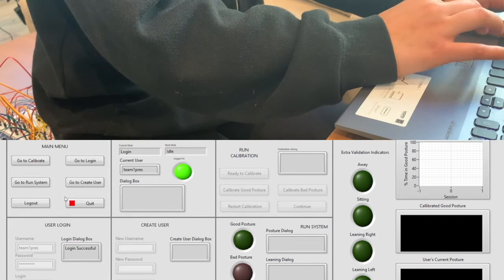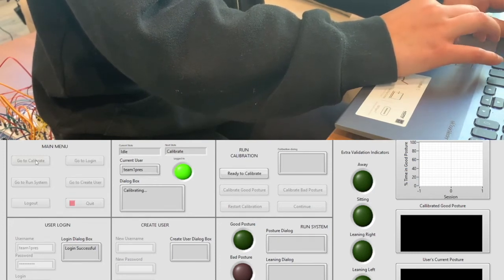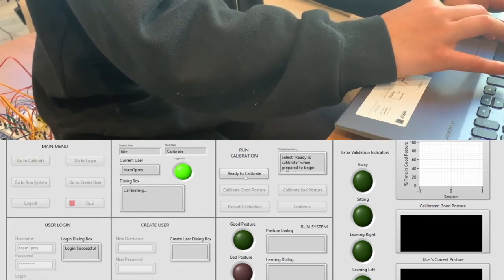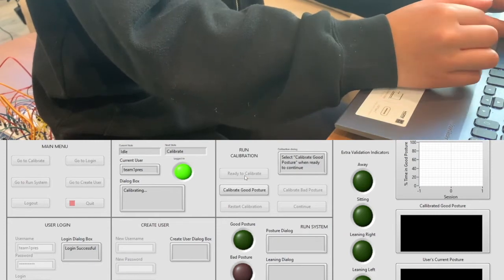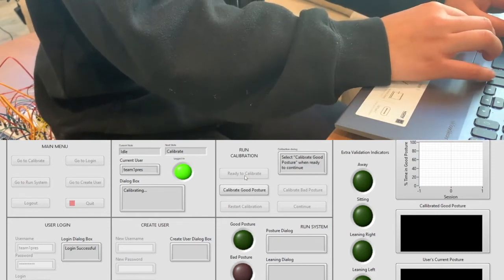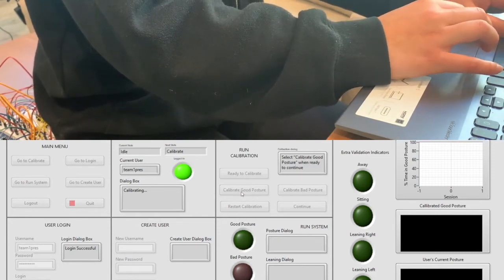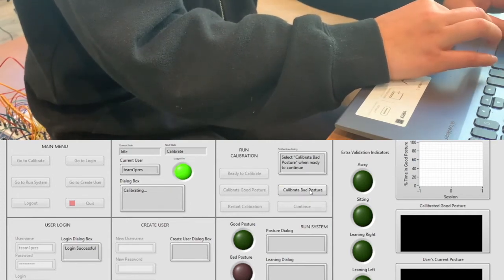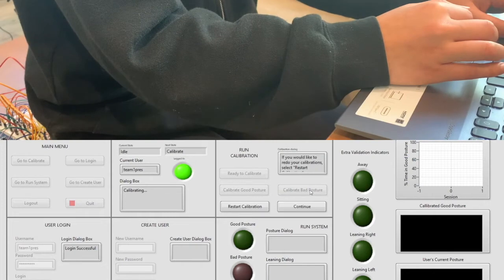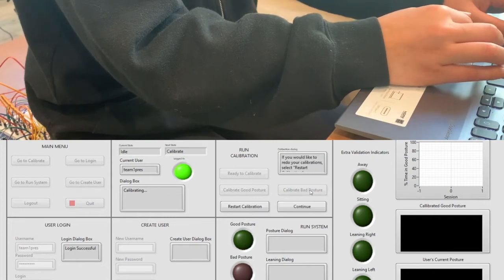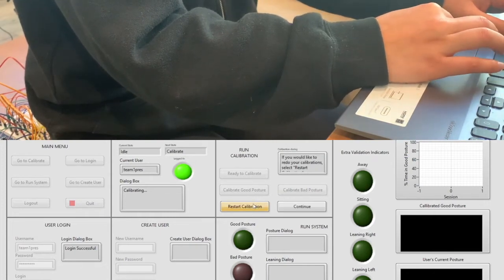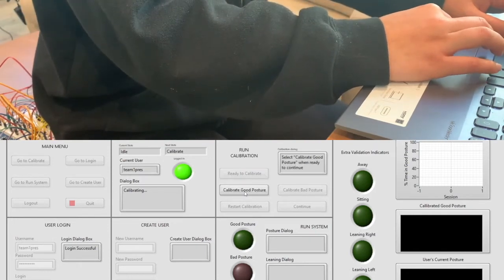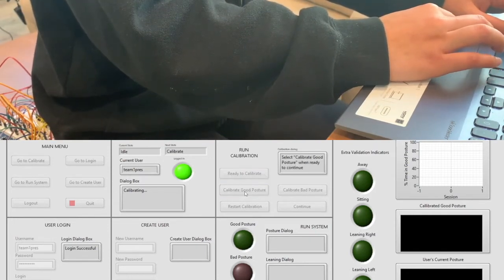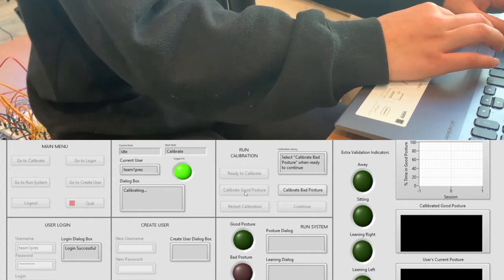Now that you are logged in, you're ready to create some calibration data. Click Go to Calibrate to enter the calibration phase of the device. Click on Ready to Calibrate, indicating that you want to record a calibration session. Once you're sitting with good posture, select Calibrate Good Posture. Then sit with bad posture. Select the Calibrate Bad Posture. The device will record your weight distribution with bad posture. If you feel as if your calibration data might be skewed, you can always recalibrate. So what you're going to do is click Restart Calibration and run the whole process all over again.